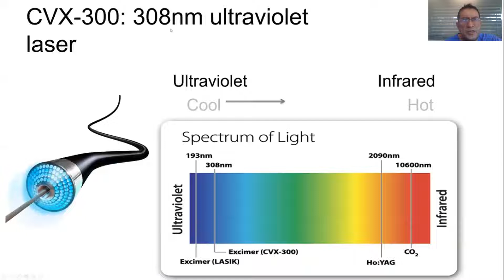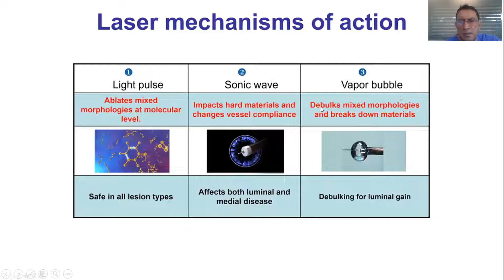The ultraviolet light is a 308 nanometer ultraviolet, and the laser mechanism of action is that it works through the light pulse, sonic wave, and through the vapor bubble. Now, light pulses, when light is transmitted from the machine into the catheter tip and up to the plaque, help in ablating the atherosclerotic plaque. And the sonic wave will actually impact the calcified hard material, and it also changes the compliance of the vessel, and the vapor bubble will actually debulk the plaque, and therefore there will be a gain in the lumen of the coronary artery.